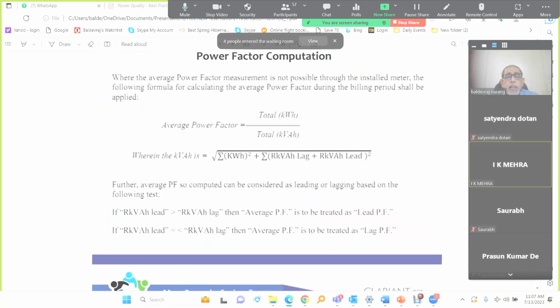So this is how we go from the initial to the final power factor. And then the billing, as I said, the leading power factor is also taken into account these days while calculating the power factor and the kVAh value, because the leading was creating a problem. The meters used to be locked at unity power factor, and above that everything was considered unity, but that was creating a problem. So that's why the RKVAh lead is also measured today, and we get the true kVAh value.